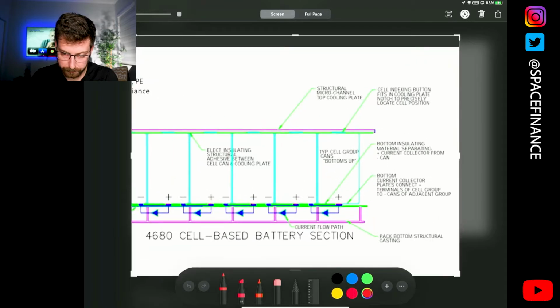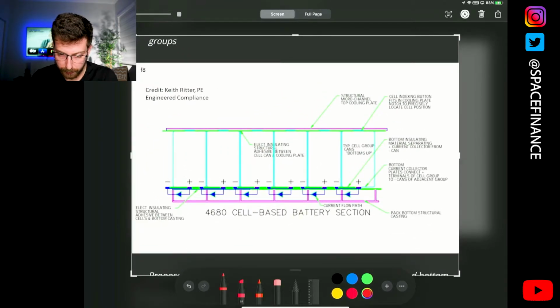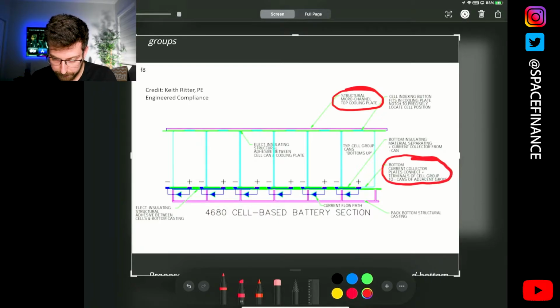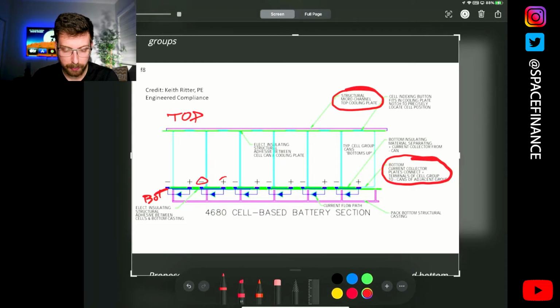So this right here is very important. You get a structural micro channel, that's the top plate, a plate to cool it. And then you also have the bottom plate. You need to cool the top of the battery too. This is the top, and that would be the bottom. Essentially you connect them in a way where your cathode and anode are connected through a flow path of the current, and then you have insulating epoxy and insulating plates between the actual plates.